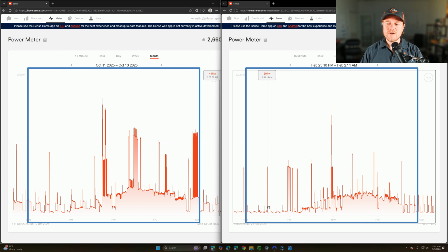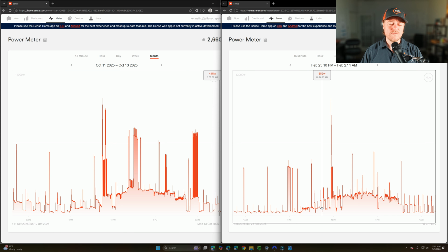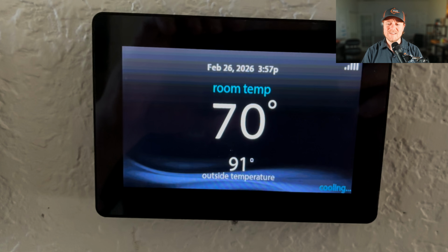Then over here in February, we can see that the system didn't cycle until around 9:30 a.m. And the cycle times are also a lot shorter. That's telling me that we have a lot smaller of a heat load on the house, even though the outdoor temperatures are very similar. In order to get the system to run to make some sort of comparison, I lowered the thermostat temperature to 70 degrees, 2 degrees lower than my previous test, just to get the system to run a little bit more.